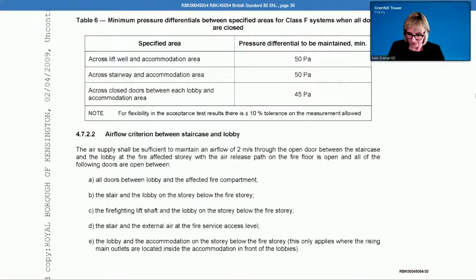Well, I think it is stating that that is a satisfactory test. Well, it's saying it's satisfactory for fire dampers, which are the lowest performance level of damper, but it's not the same as a smoke control damper, is it? It's not as high a standard. What they're doing is giving you a list of possible standards that you could use, and right at the end, they're giving you this older standard that was still regarded as suitable at the time. What happens is you get a lot of development of products and test standards as well, and you've still got a legacy product, a legacy standard that exists. So they're still allowing you to use that standard below. But obviously, if you wanted to go for the modern standard, you'd go for the one above. Generally, these older standards get written out as time goes on. That's just the way standards work.